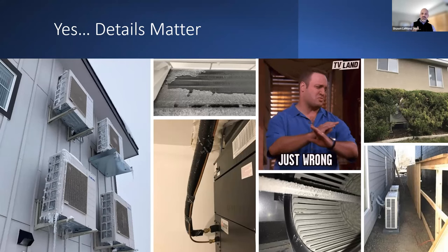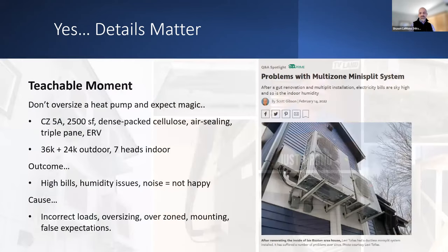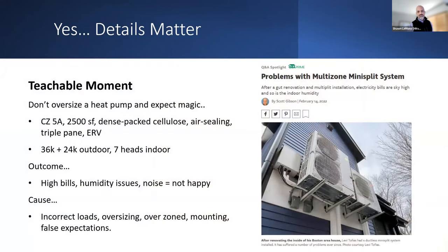And then a few other items about airflow, making sure you've got good airflow around the outdoor units on the right side, a tall fence, tight space, maybe not lifted up off the ground for clearance for ice and snow buildup, et cetera, all considerations. And then also dust and debris, maybe during construction or remodel. It's hard to see in that image, but I'm looking inside a unit, I'm taking a picture of a fan, and you can see a swipe of my finger across that fan just removing a bunch of dust. And that's really hard on the coils to make them operate long-term properly.